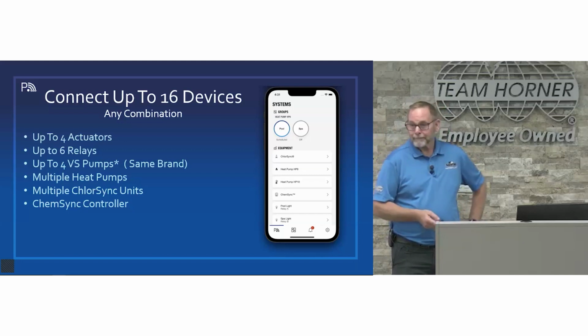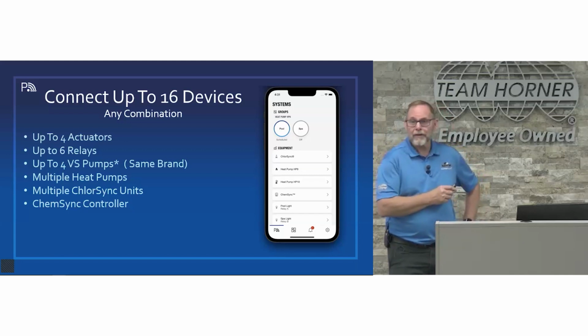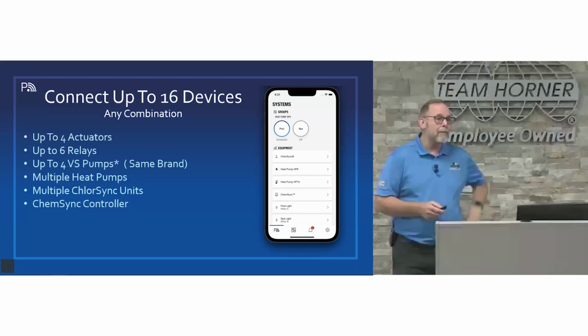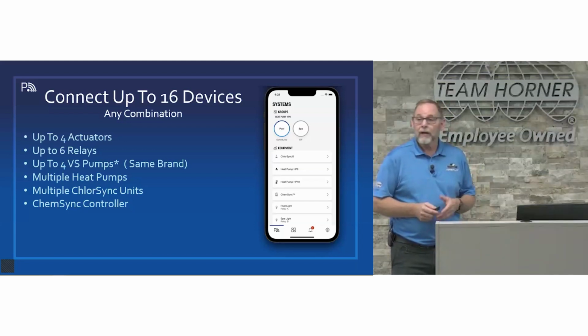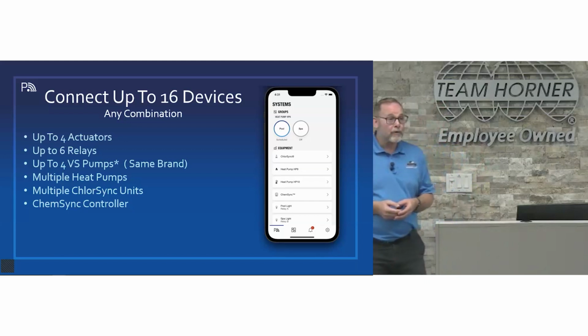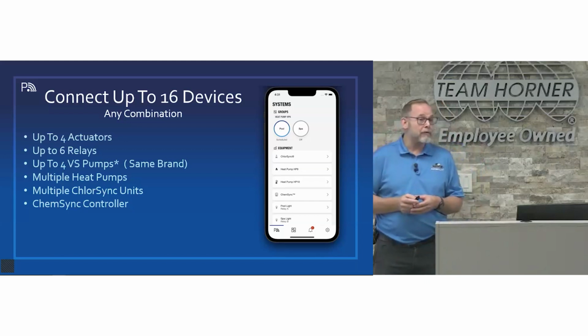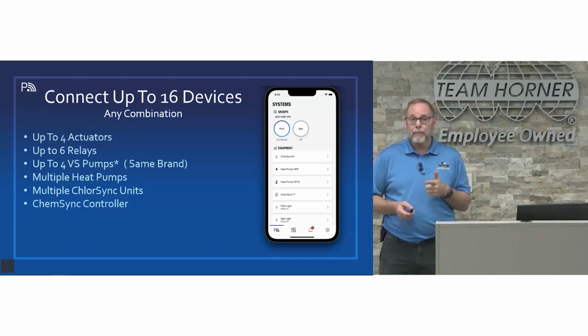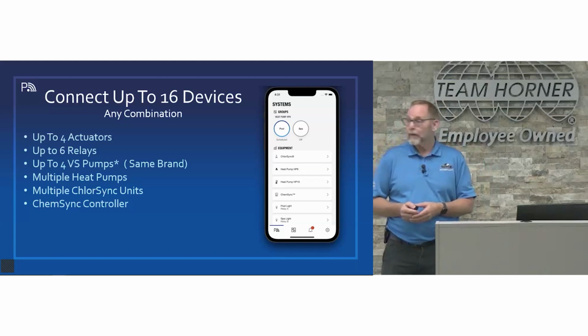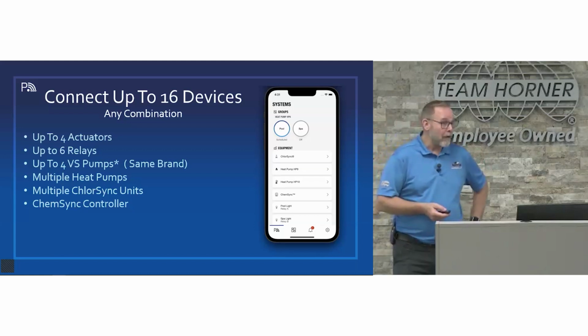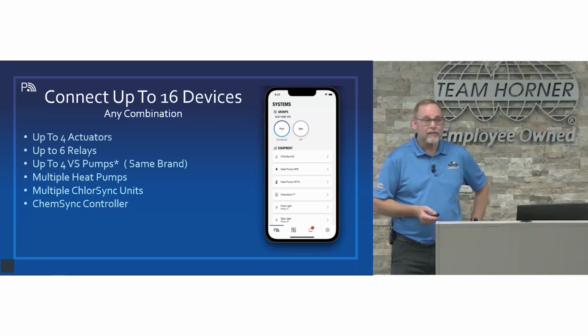Since you mentioned gas, any of the smart controller equipped heat pumps also function as a full solar controller. We can add a roof sensor and a valve actuator for full solar control, with a few different modes of operation: solar only, heat pump only, or a hybrid mode where you choose two different temperatures and it uses solar as much as possible, kicking on the heat pump to back it up if it falls too far below the set point. That's a feature we've always had that a lot of people don't realize is available, but it's built in.